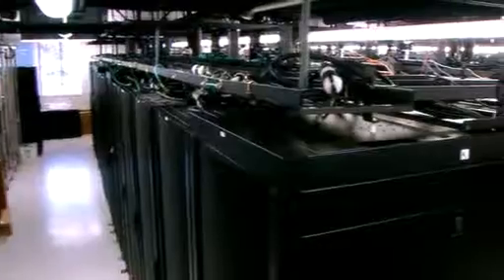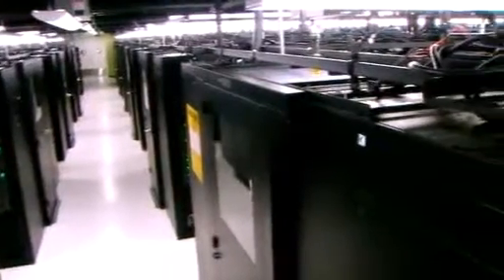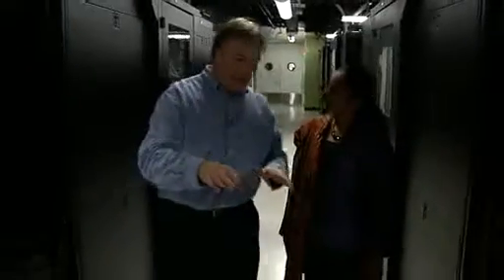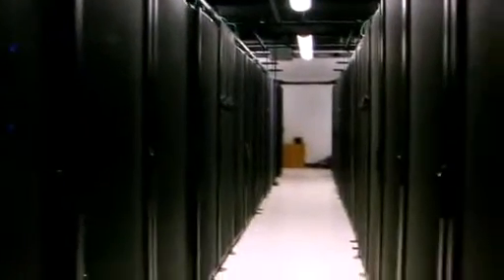The data center of the future will be a warmer place. It will be a place that is less made to pamper the IT equipment, but to focus much more on functionality and on efficiency and flexibility. If you notice the temperature in here, it's 74 degrees Fahrenheit. So we can run it warmer because we're containing the heat. And every degree that you increase that temperature Fahrenheit-wise is a 4% efficiency gain all the way through to the plants. So this data center, as we were saying, is the highest density in here.